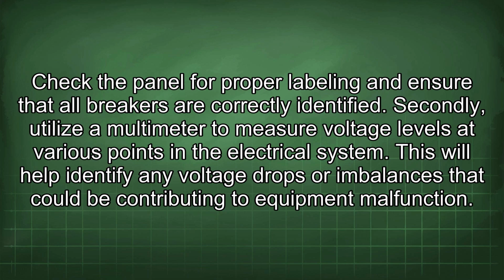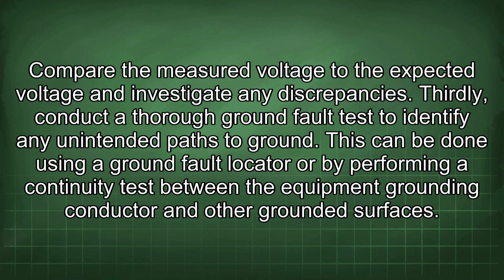Secondly, utilize a multimeter to measure voltage levels at various points in the electrical system. This will help identify any voltage drops or imbalances that could be contributing to equipment malfunction. Compare the measured voltage to the expected voltage and investigate any discrepancies. Thirdly, conduct a thorough ground fault test to identify any unintended paths to ground.